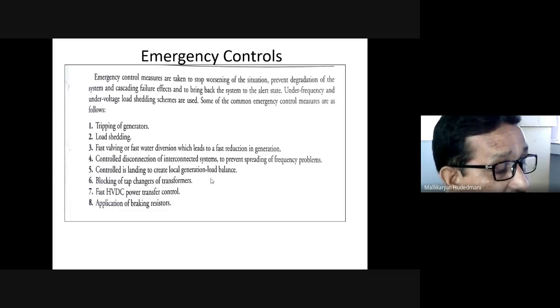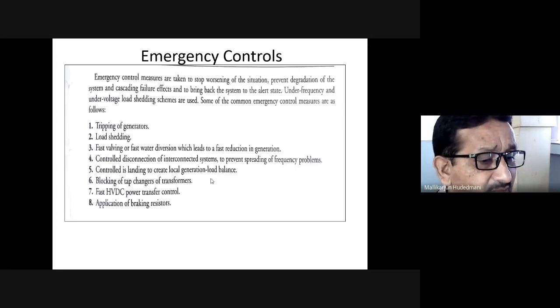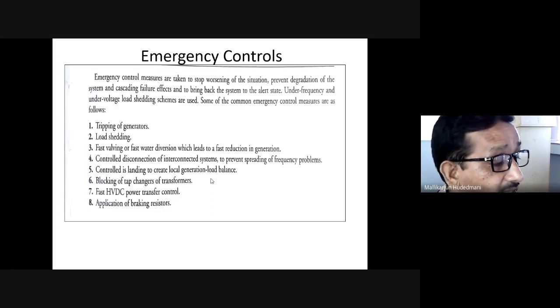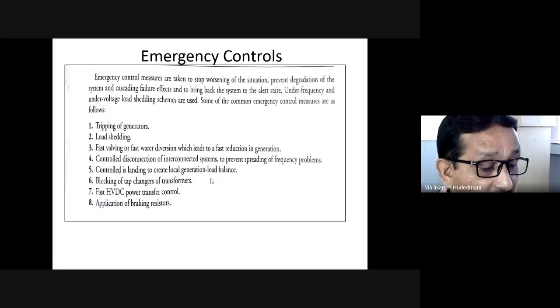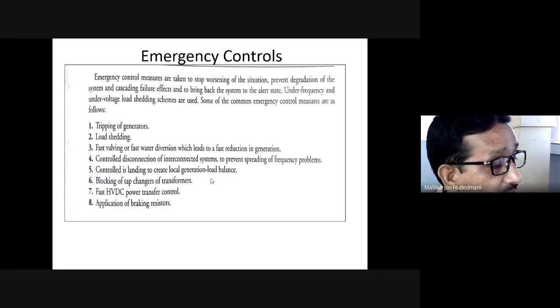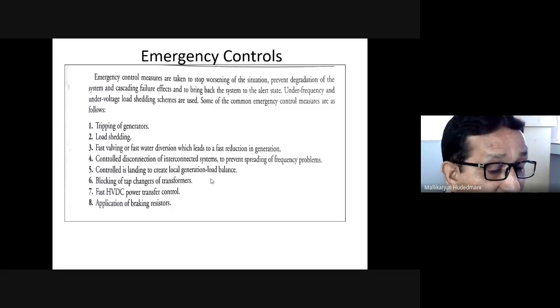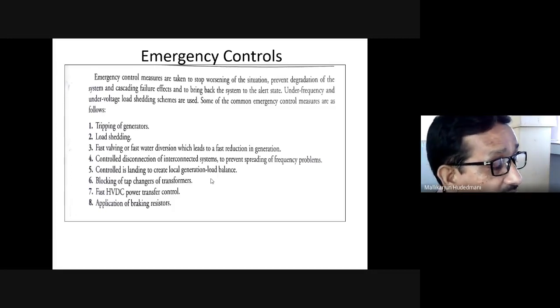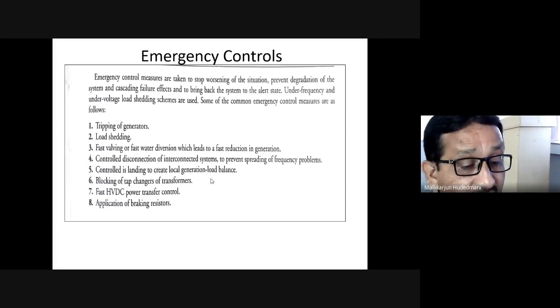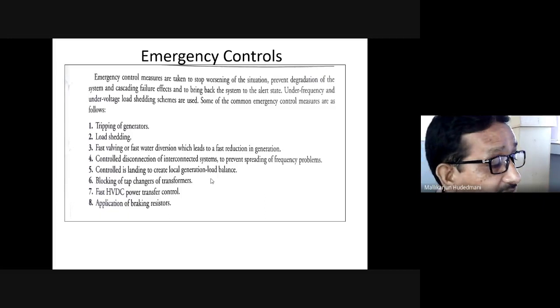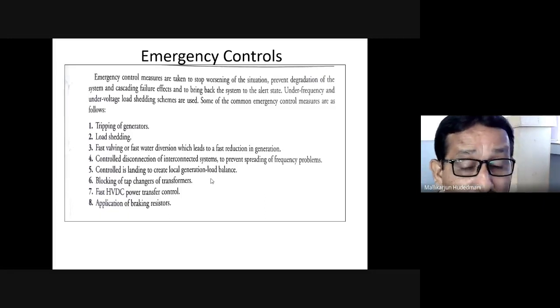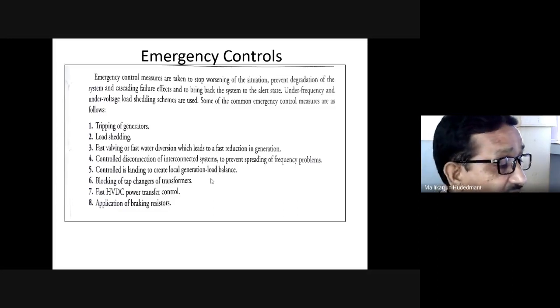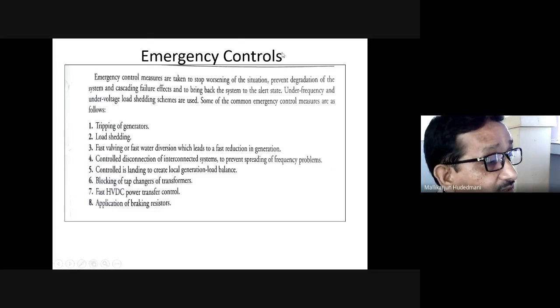Naturally, when we have a disaster or a drop in voltage due to any other reason, maybe a fault, maybe lack of reactive power, the transformer comes into the picture to shift the working voltage by the automatic tap changer concept. The tap changer is a facility connected to the power transformer which automatically senses the terminal voltage and shifts the tap number, so that a delta V added to the terminal voltage boosts it to the required level of voltage. Tap changers may start hunting, adding more and more steps to the actual voltage to try for the best terminal voltage. In that regard, tap changers hunt too much and may fail, and might cause damage to the interconnections. So blocking of that is one of the important aspects under emergency control.